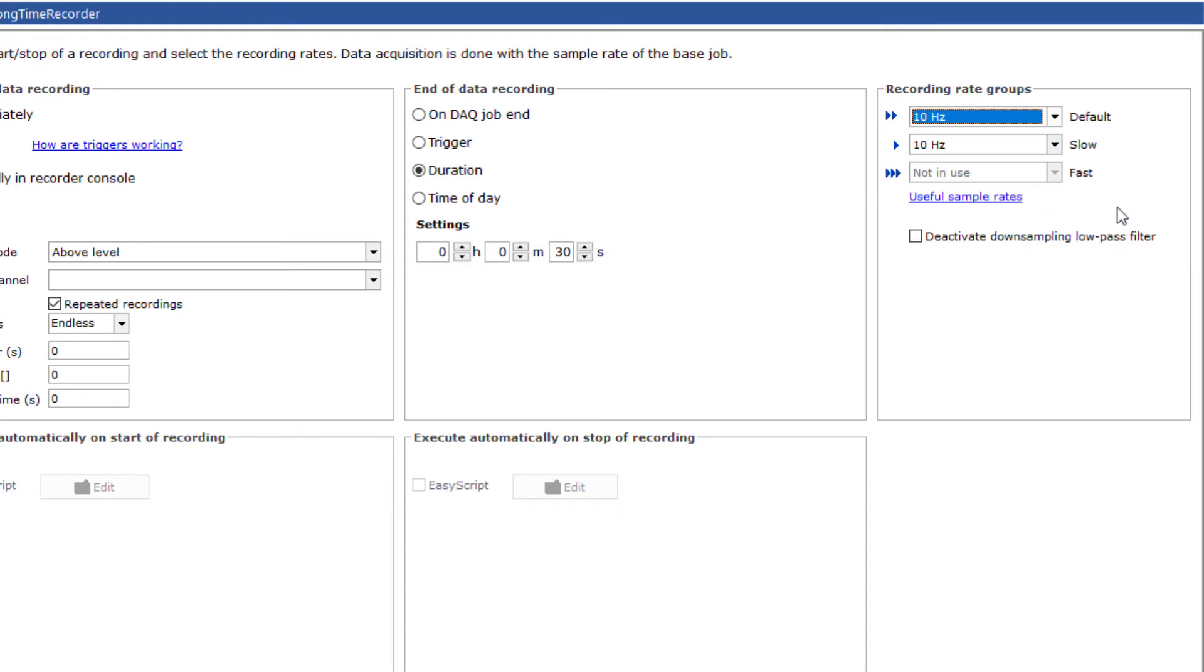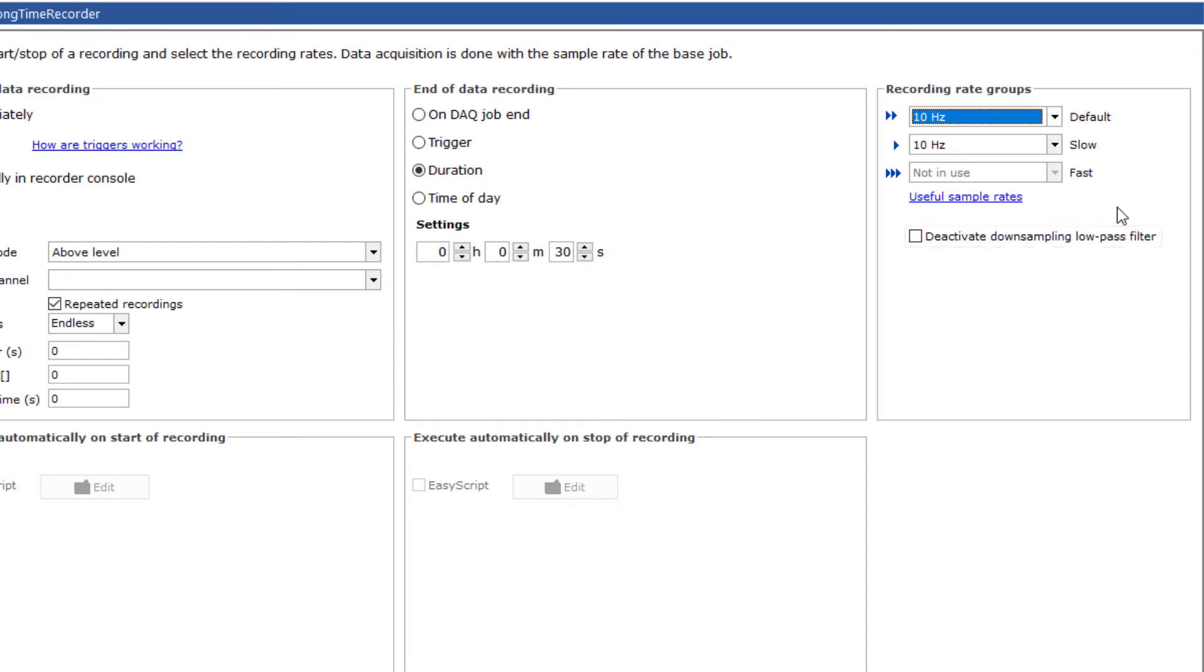The recorders offer the ability to reduce the data. You can control how Catman reduces the data with this box. Catman uses a low-pass filter by default. If this is not what you want, check this box. If you check it, every 1,000th value will be saved. All other values are ignored.